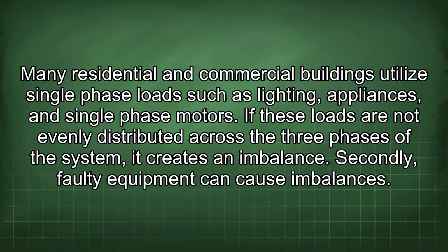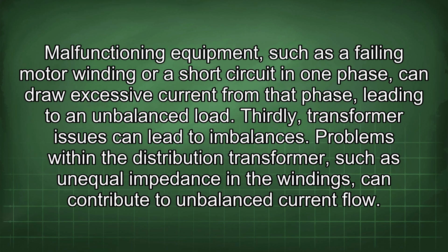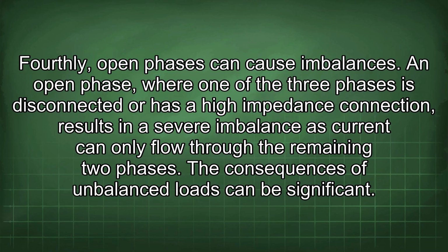Secondly, faulty equipment can cause imbalances. Malfunctioning equipment, such as a failing motor winding or a short circuit in one phase, can draw excessive current from that phase, leading to an unbalanced load. Thirdly, transformer issues can lead to imbalances. Problems within the distribution transformer, such as unequal impedance in the windings, can contribute to unbalanced current flow. Fourthly, open phases can cause imbalances. An open phase, where one of the three phases is disconnected or has a high impedance connection, results in a severe imbalance as current can only flow through the remaining two phases.